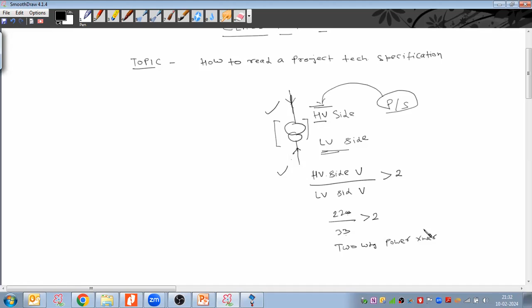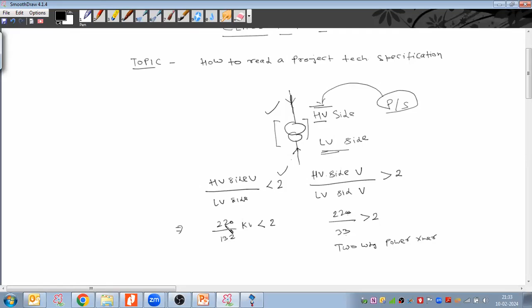Two winding type power transformer. At the same time, whenever my HV side voltage to LV side voltage ratio is less than 2, for example, I have a 220 by 132 kV substation. If you divide, this will come less than 2. In that case, we use an auto transformer.